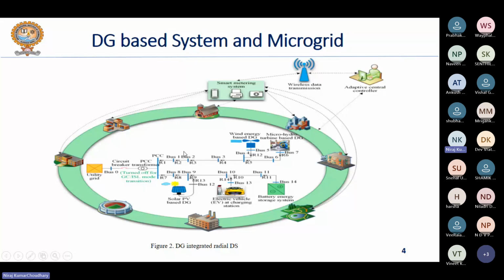So here through this diagram, we can see that we have considered a standard 9 bus Canadian benchmark system where different types of renewable energy sources like solar photovoltaic based DG and wind turbines are there. Hydro turbine based DG is also installed. EV charging stations are also there. Some storage in the form of a battery energy storage system is also present. And in this system, you can see the PCC bus here. After the PCC bus, you have a microgrid infrastructure, and on the upstream side you have the utility grid network, right? Now the operation of these circuit breakers enables it to operate either in the grid connected mode or in the islanded mode of operation. So this is one of the basic diagrams of a microgrid system.